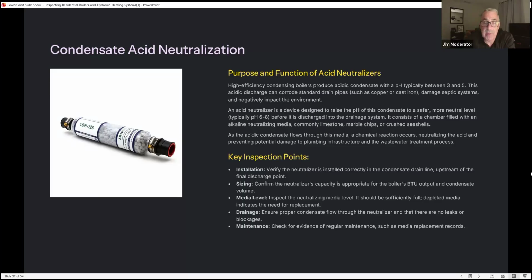The key inspection points: make sure it's installed, and confirm the sizing is appropriate for the boiler's BTU. Media level: inspect the neutralizing media level. It should be sufficiently full. A depleted media level indicates need for replacement. That's how many pellets and such are in there, and the size of them. Drainage: ensure proper condensate flow through the neutralizer, that there are no leaks or blockages, and check for evidence of regular maintenance, such as media replacement records.